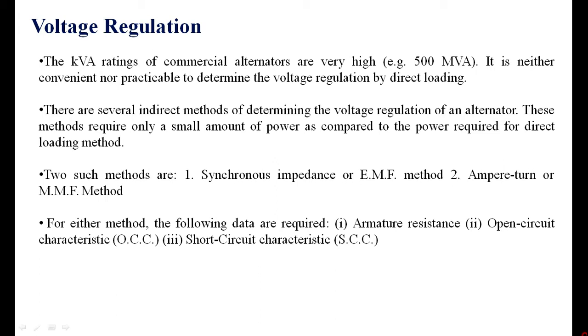For either the EMF method or the MMF method, the data required are three: one is the armature resistance, the second is the open circuit characteristics (OCC), and the third is the short circuit characteristics (SCC). These three data are required to determine the voltage regulation by either method.